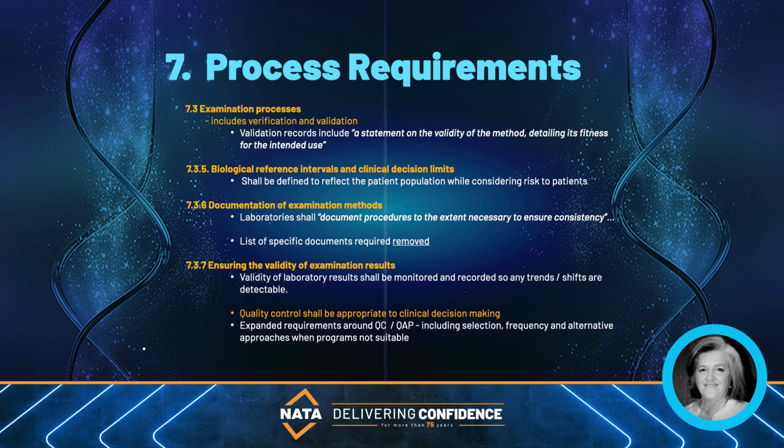Biological reference intervals and clinical decision limits shall be defined to reflect the patient population while considering risk to patients. They shall be periodically reviewed and changes communicated when applicable. Labs shall document procedures to the extent necessary to ensure the consistent application of activities and the validity of results. If abbreviated documents are used, they shall correspond to the procedure, and all documents associated with processes shall be document controlled.